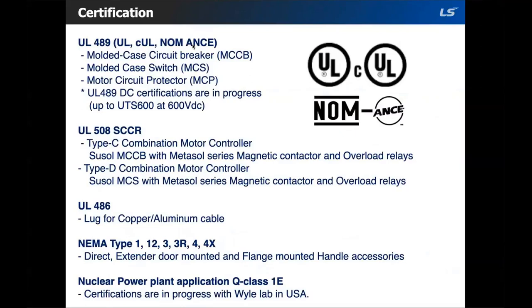These are all the certifications for the MCCB: UL 489, UL 508, and UL 486 for the lugs. NEMA types offered are Type 1, 12, 3, 3R, 4, and 4X. There is also a nuclear power plant application certification, Q-class 1E — I'll check on the current status of that and let you know.